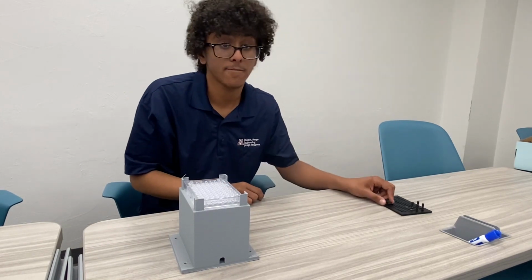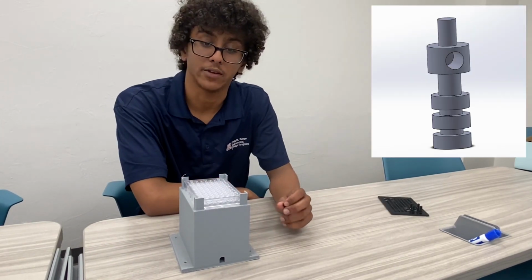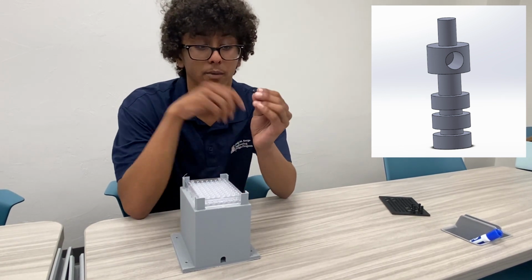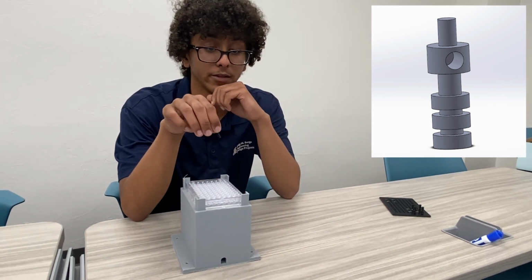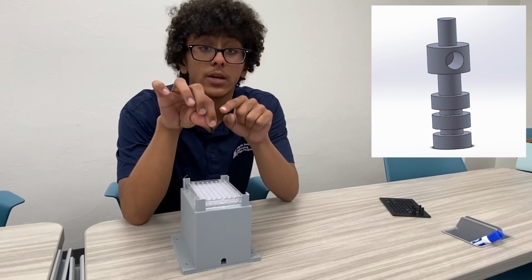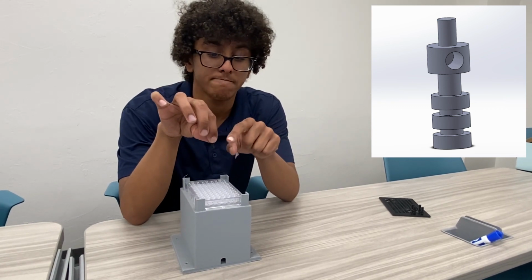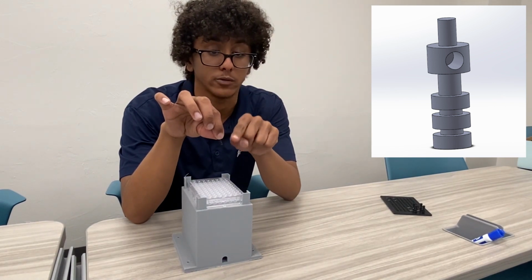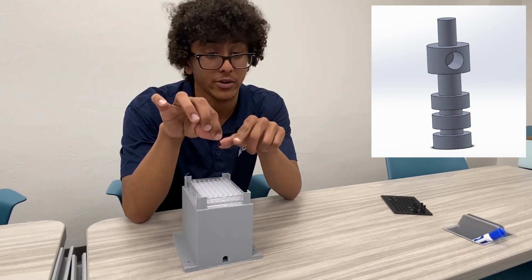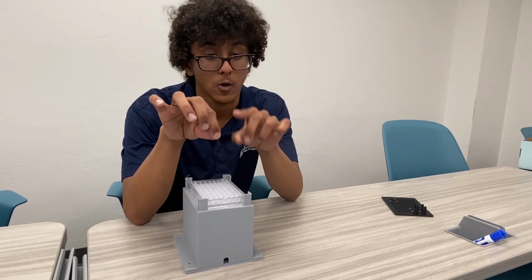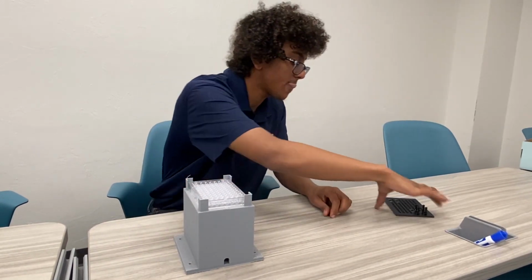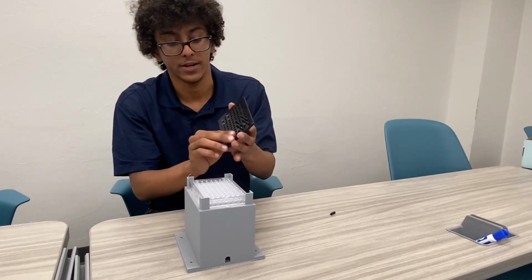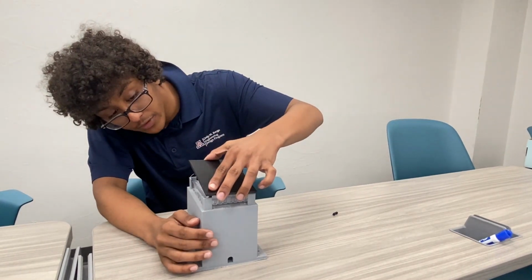Outside of the housing, something has to respond to the drive magnets to impart shear in the fluid within the wells. That takes us to the spinning bobble piece, responsible for mechanically agitating platelets. After several prototypes, here's the final model used for the bobble, 3 discs stacked on top of each other with space between to trap the fluid within. In cylindrical shape to maximize surface area, ensuring abrasive collisions with the surface of the piece consistently. There are 4 of these bobbles embedded within the plate lid, and here's how the whole assembly comes together.